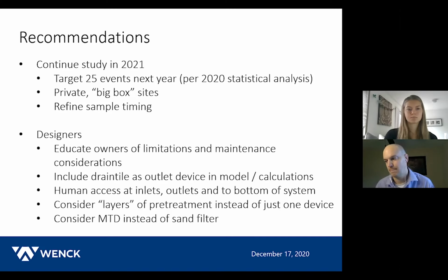working. And then finally, I'm not trying to promote an underground sand filter or an MTD. I just want to point out that considering an MTD, a manufactured treatment device, instead of the sand filter, that MTD can be placed almost adjacent to your storage, so you have easier access to that. You can clean, you can refurbish the MTD more easily, perhaps more costly, I understand that, but that can be accomplished probably at less cost and easier than replacing that sand filter layer below your storage.